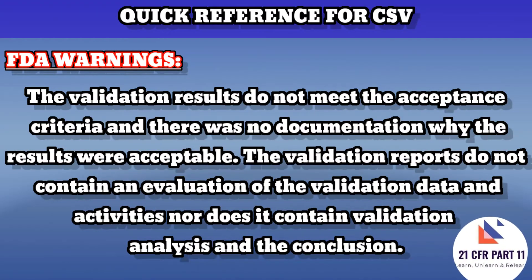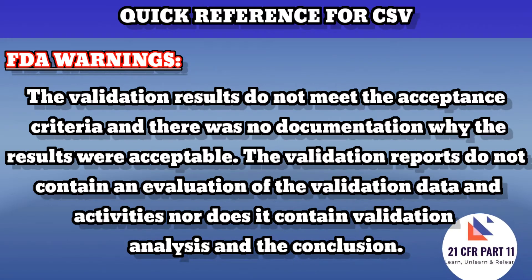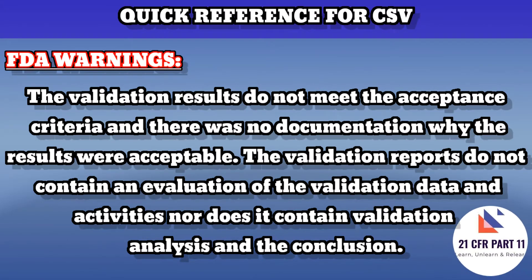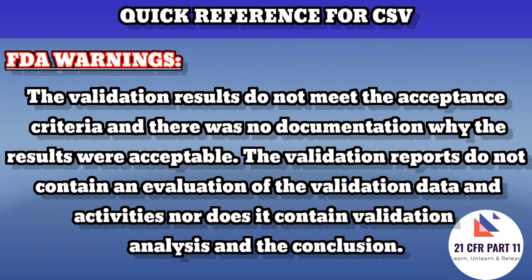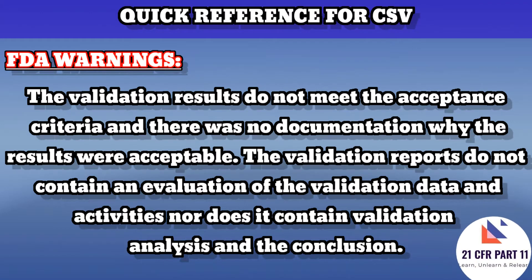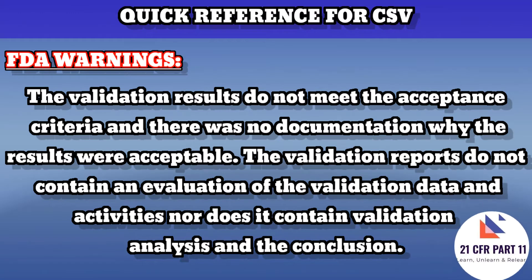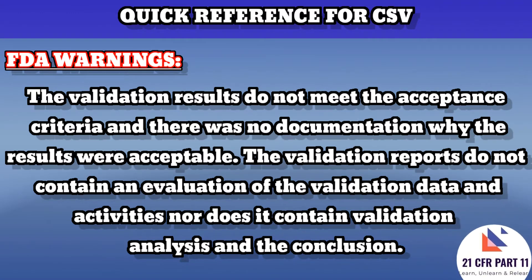The last FDA warning states that the validation results do not meet the acceptance criteria and there was no documentation explaining why the results were acceptable. The validation reports do not contain an evaluation of the validation data and activities, nor do they contain validation analysis and conclusion. This FDA warning is purely related to test results not meeting the acceptance criteria.